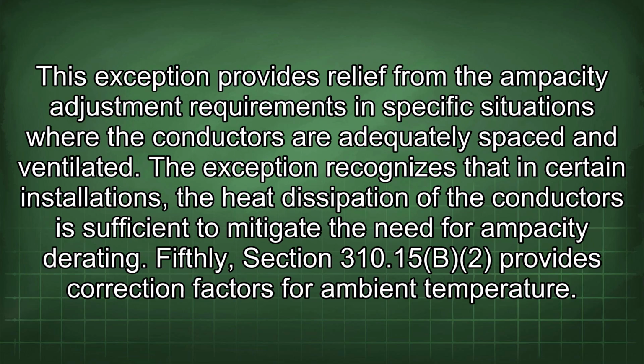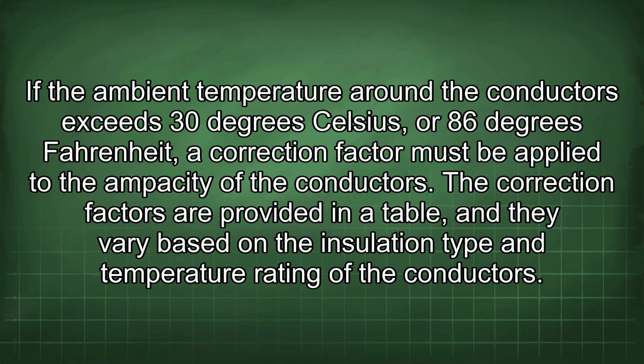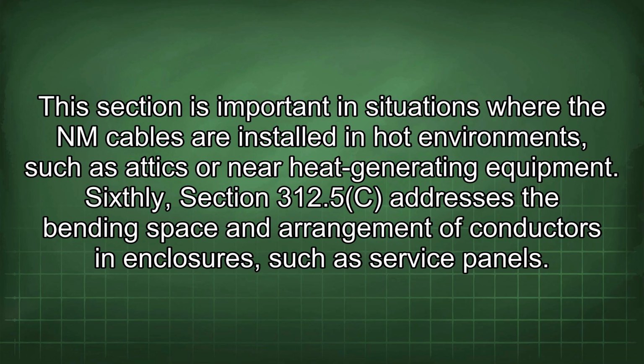Fifthly, Section 310.15(b)(2) provides correction factors for ambient temperature. If the ambient temperature around the conductors exceeds 30 degrees Celsius, or 86 degrees Fahrenheit, a correction factor must be applied to the ampacity of the conductors. The correction factors are provided in a table, and they vary based on the insulation type and temperature rating of the conductors. This section is important in situations where the NM cables are installed in hot environments, such as attics or near heat-generating equipment.